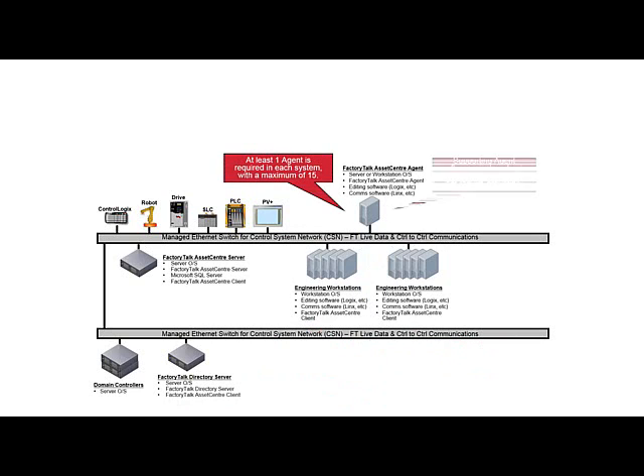The final component is the FactoryTalk Asset Center agent. At least one agent is required in each FactoryTalk Asset Center system, with a maximum of 15 as of version 6.0. The agent is used for any scheduled tasks, such as a search or a disaster recovery schedule. When used with disaster recovery, an asset's configuration software must be present as well. For example, ControlLogix assets require Studio 5000 Logix Designer and RSLinx Classic. No software package requires activation when used for disaster recovery purposes.